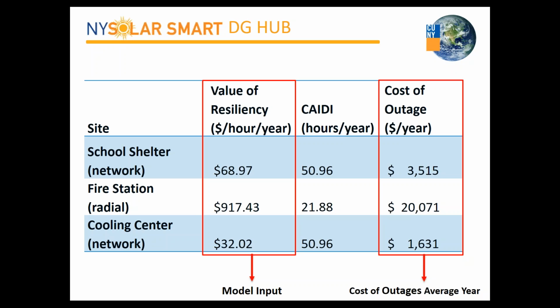economic scenarios. So one thing I wanted to point out here is that there's a large difference on the Con Edison grid between the network and the radial grids. The radial grid has a much higher value of resiliency than the network grids, and the reason for that is because the network grids are much more reliable than the radial grids. So the value of resiliency is higher on the radial grid, because there are just more outages and more opportunity to improve reliability on the radial grid than there is on the network grid.